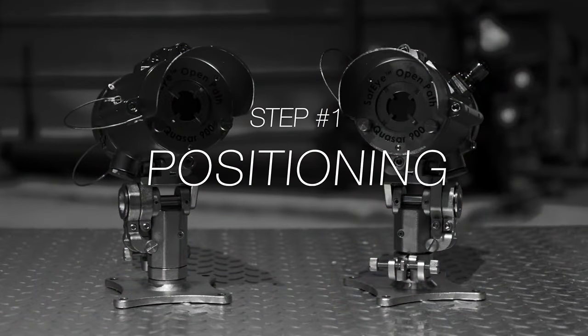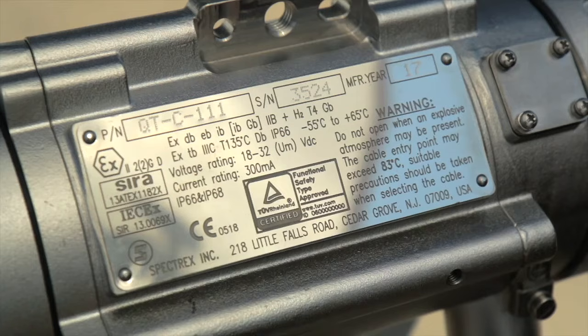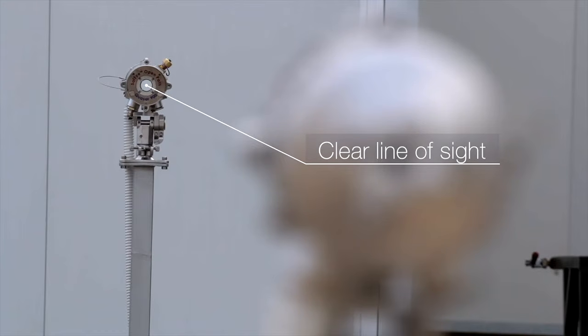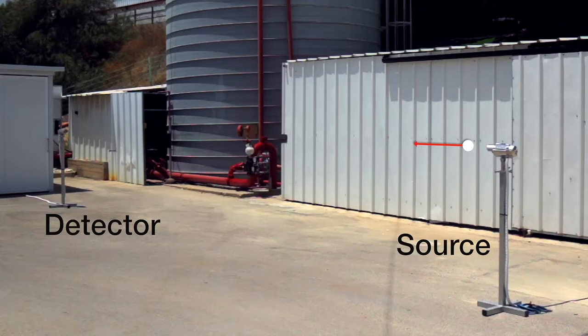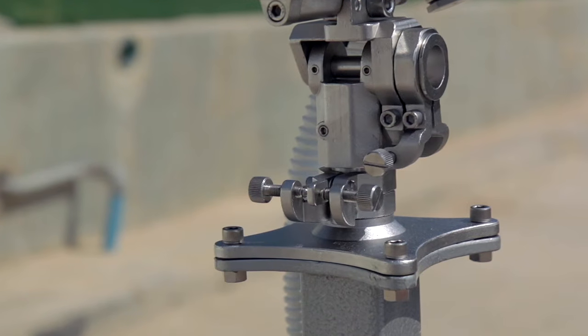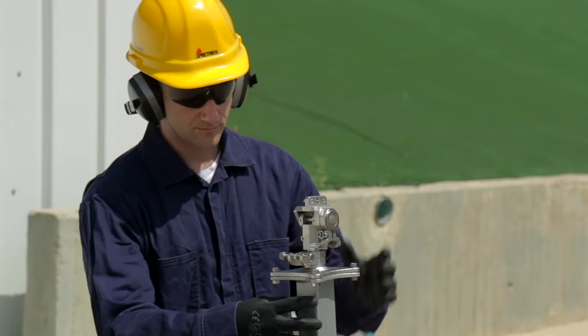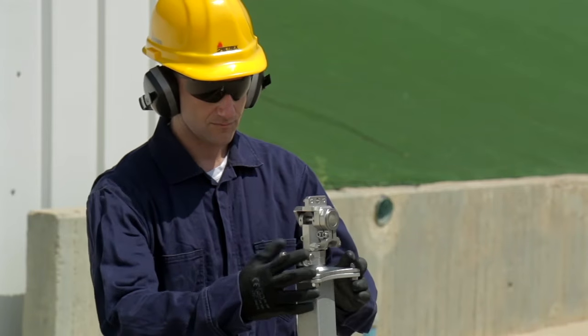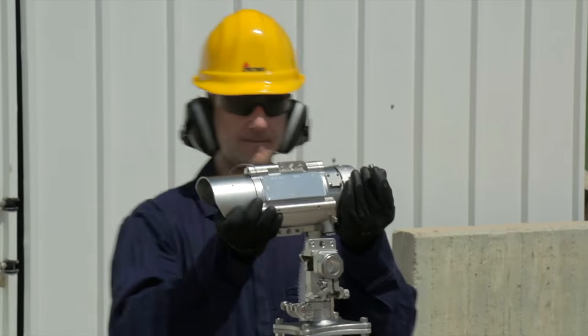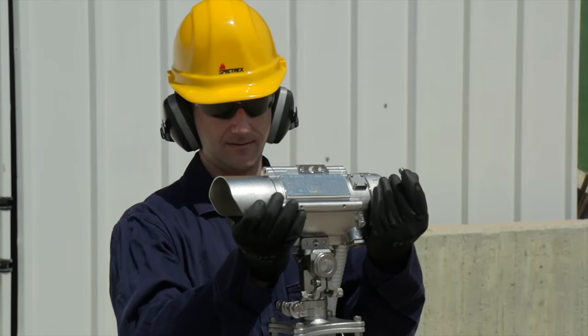Positioning. First, verify that you are using the correct source type and have a clear line of sight between the source and detector. We offer different source models to support a wide variety of coverage ranges. Measure the distance between the source and detector installation points and verify that it fits the range of the source model you have. Next, make sure the unit mounting structure chosen for connecting the open path gas detection system is stable. Place the source on the tilt mount and verify the 2 pins are in place.